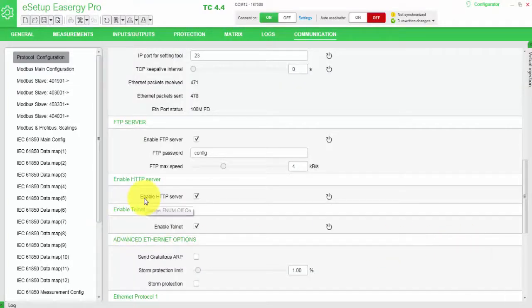An alternative solution to connect to the P3 protection relay from Schneider Electric to Easergy Pro is to use the web browser interface. You do not need the setting tool at all and you can use your browser. In order to use it, you need to enable one parameter under Communication where 'Enable HTTP Server' has to be ticked and activated.